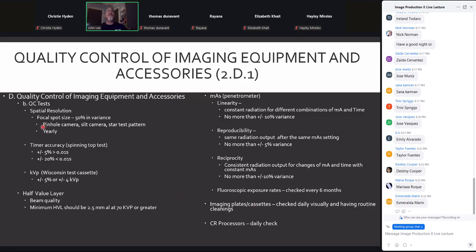For spatial resolution, focal spot size, you're allowed a 50% variance. The pinhole camera, slit camera, and the star test pattern are the tests for spatial resolution. The easiest, most popular one to do is the star test pattern. This should be done yearly. Timer accuracy would utilize an electronic synchronous spin top. For settings greater than 1/100th of a second, there's a 5% plus or minus variance in the timer setting. For times less than 1/100th of a second, there's a 20% margin of error for variance.